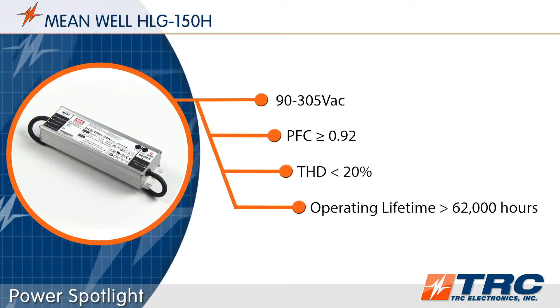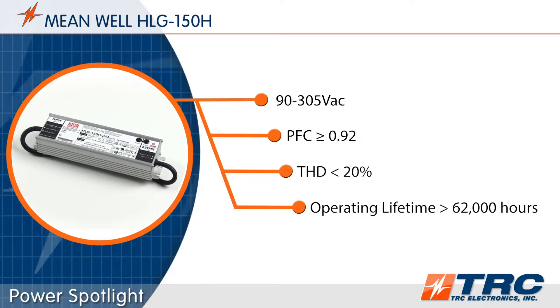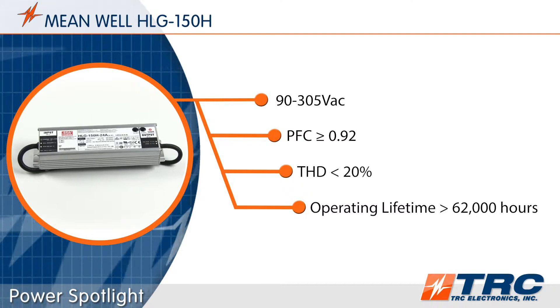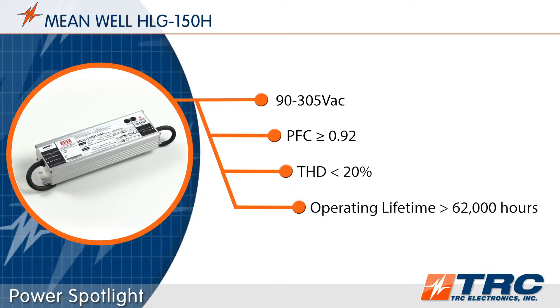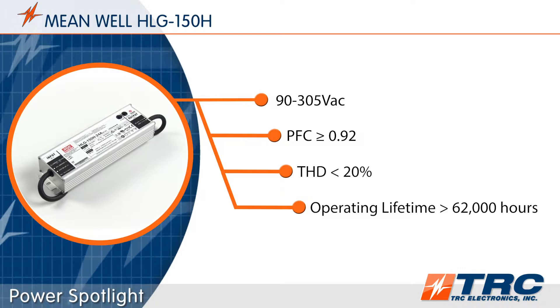All models feature a wide input voltage range of 90 to 305 volts AC, which means that these drivers can operate in 120 volt, 220 volt, or 277 volt lighting systems. These great performance features will help lighting designers meet the DesignLights Consortium standards for solid state lighting that exist at the time of this recording.